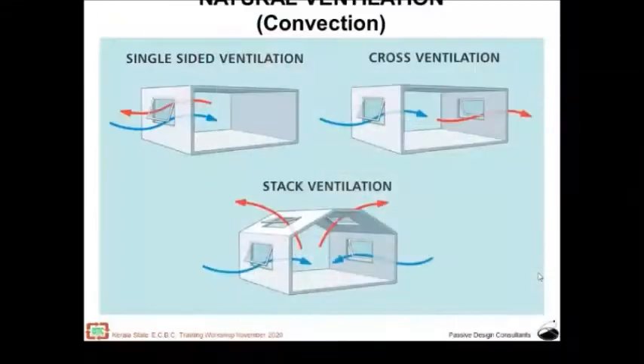stack ventilation, where we allow cool air to come through the bottom and let the hot air rise from the top, allows an even better mode of ventilation. It leads to an even higher rate of ventilation. So if the building is intended to be naturally ventilated, the guidelines as given in NBC 2016 must be followed.